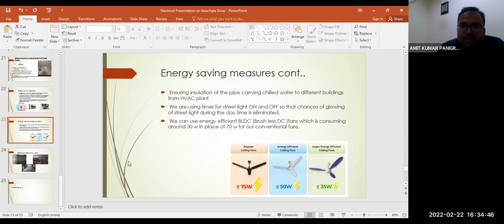And next are the energy saving measures in our HVAC system. Chilled water is going from our HVAC plant to all the academic buildings through insulated pipelines. So we are ensuring that the pipeline insulation should be intact, so that there is no heat loss during transportation. If there is a temperature loss, then there will be more pressure on the chiller unit compressor, and electricity consumption will be more. And one more thing, we are using timers for the street lights.